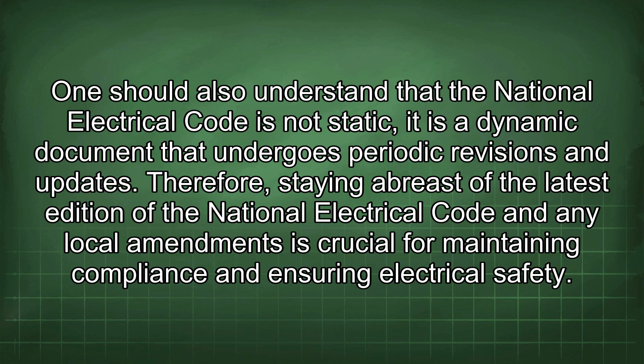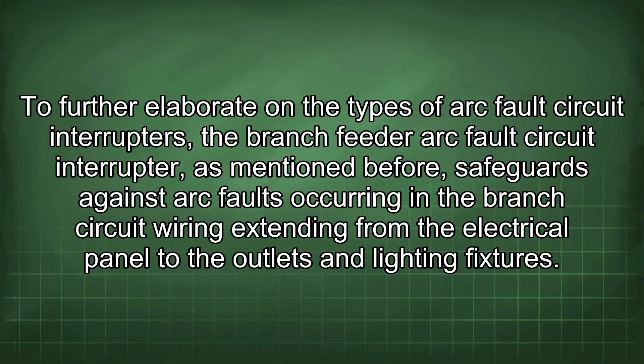To further elaborate on the types of arc fault circuit interrupters, the branch feeder arc fault circuit interrupter, as mentioned before, safeguards against arc faults occurring in the branch circuit wiring extending from the electrical panel to the outlets and lighting fixtures. The combination arc fault circuit interrupter offers a more comprehensive level of protection by detecting arc faults in both the branch circuit wiring and the appliance cords connected to the outlets.